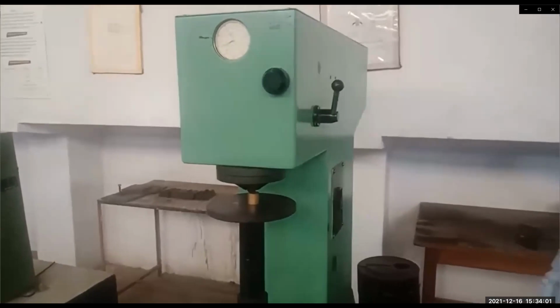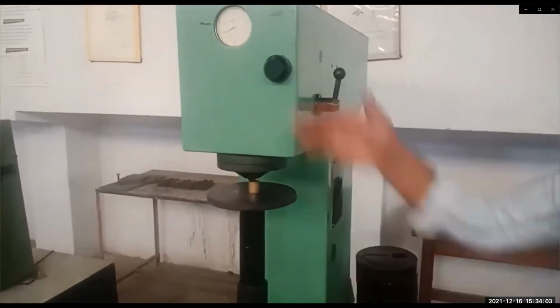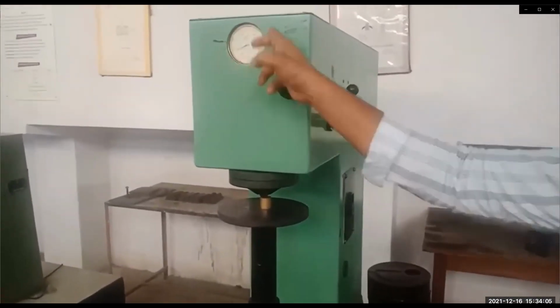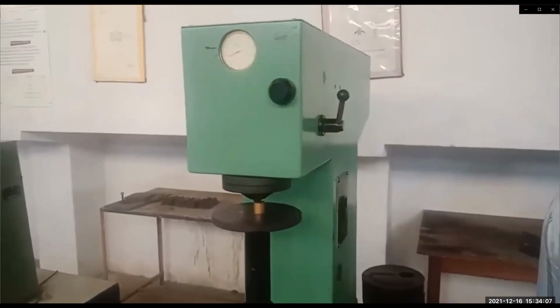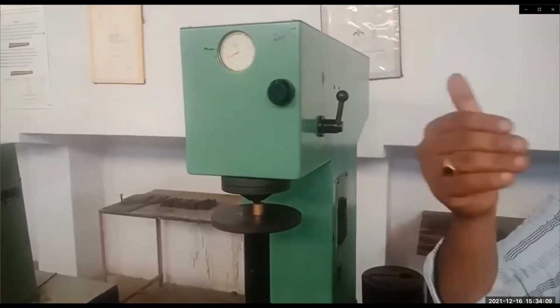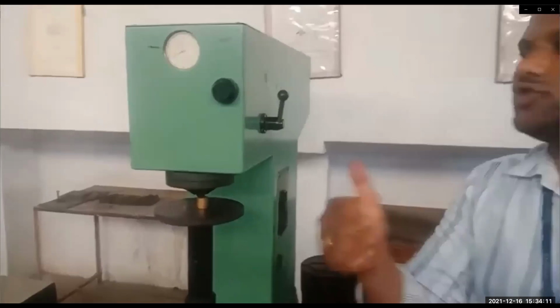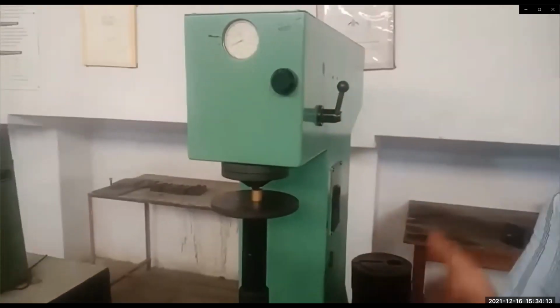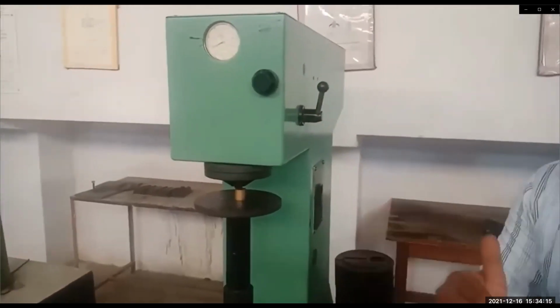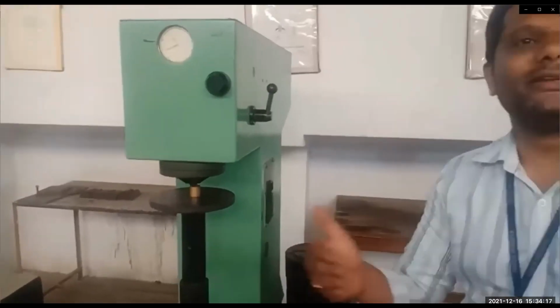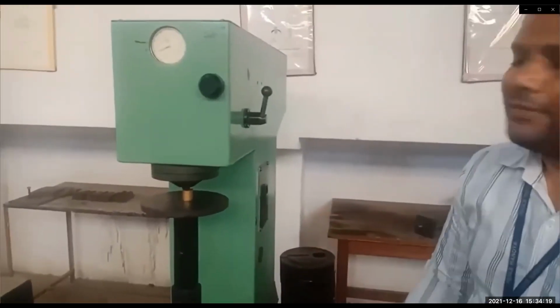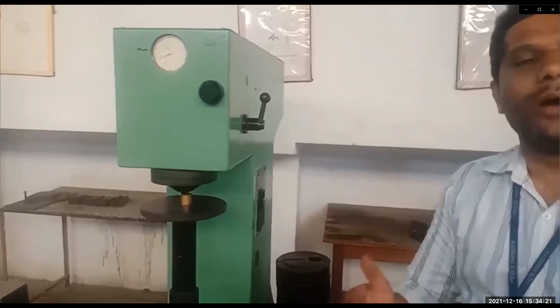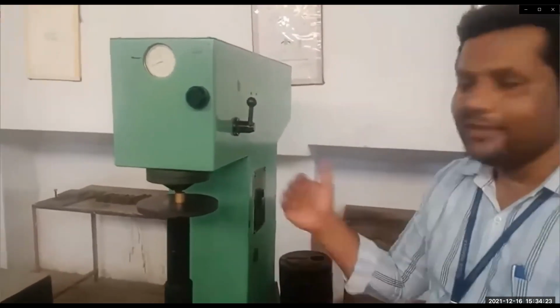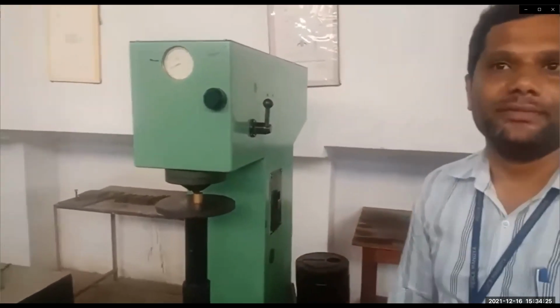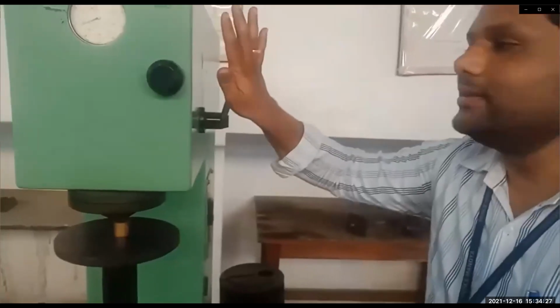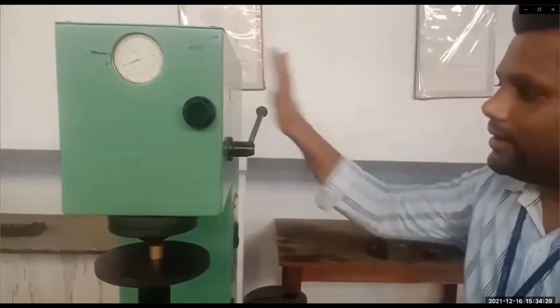Then we give the dwell time for 5 minutes, until there is a big indicator which shows the movement of the needle. Then it becomes stagnant, stable, and stops at one particular point. Until 5 minutes, depending upon the different material, we give the time. That is the dwell time. After 5 to 10 minutes, it stops. Once it stops, we release the load, then we take out the specimen. After 5 minutes, release the load.